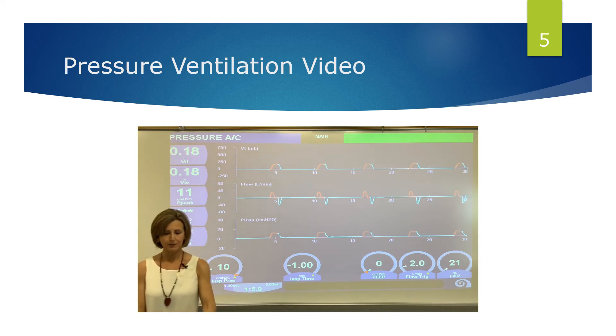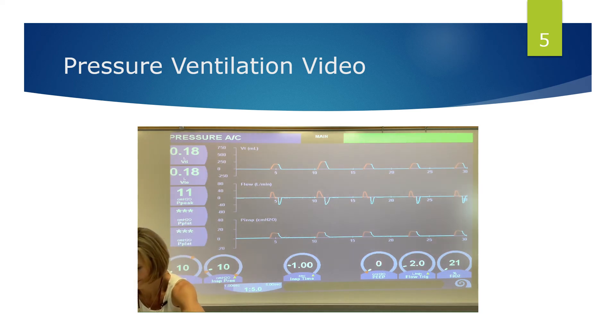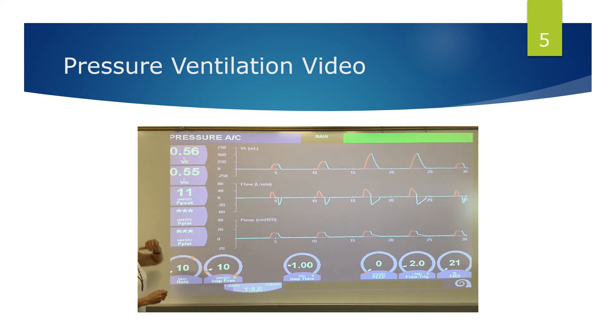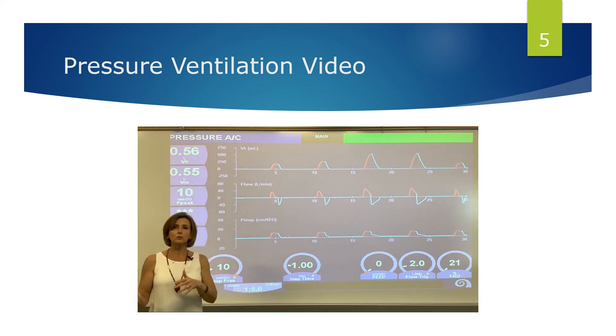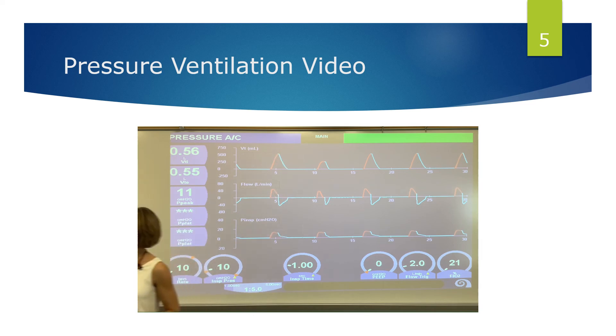I'm going to put compliance back to normal, and our volume should go back up — yeah, pretty close to what they were. Now I have normal compliance and normal airway resistance, and I'm going to simulate a mild bronchospasm — we're going to make the airway smaller and increase airway resistance.